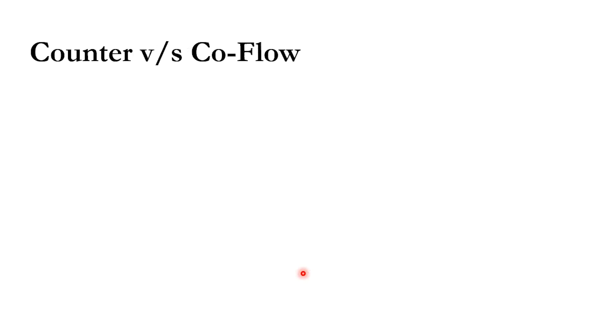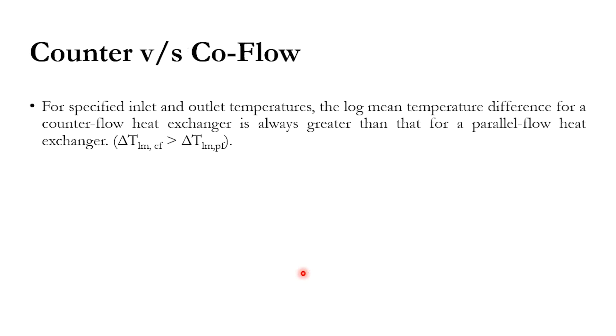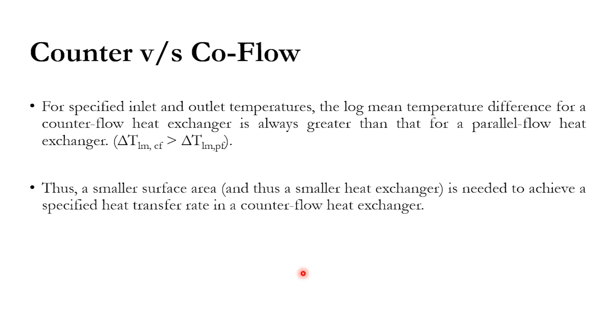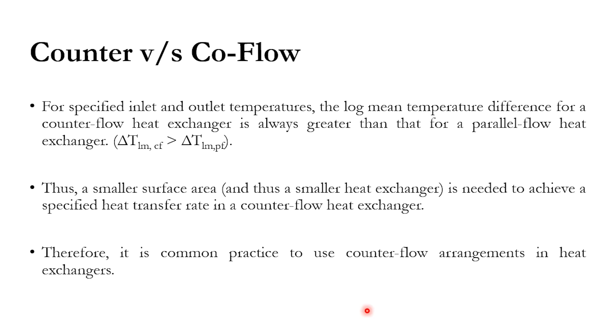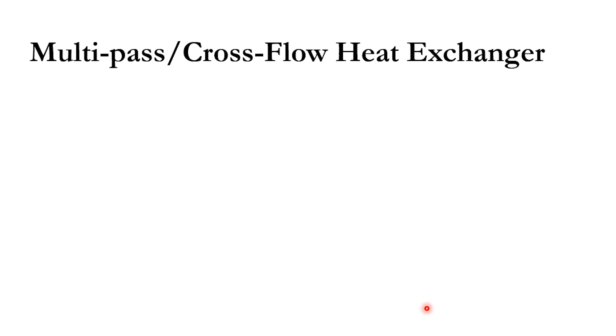Comparing counter flow versus co-current (parallel) flow: in the counter flow system, the value of LMTD is higher than in the co-current system. Looking at Q = U·A·ΔTm, if we want to compute the area A, it is inversely proportional to ΔTm. Therefore, a higher LMTD means a smaller heat exchanger area is required. Since the LMTD for counter-current is higher, a smaller area is needed compared to co-current flow. This is why it is common practice to use counter-flow arrangements in heat exchangers.